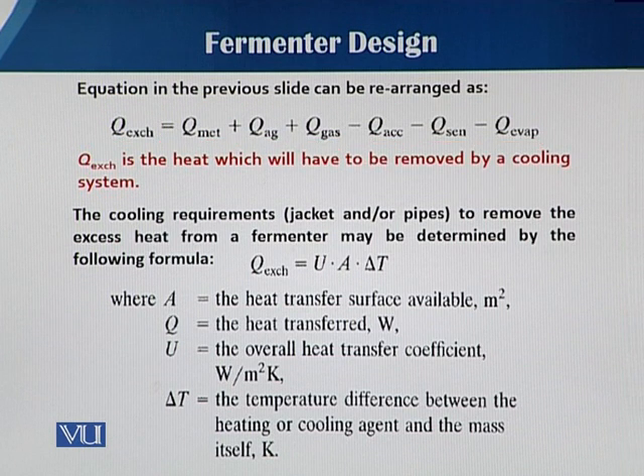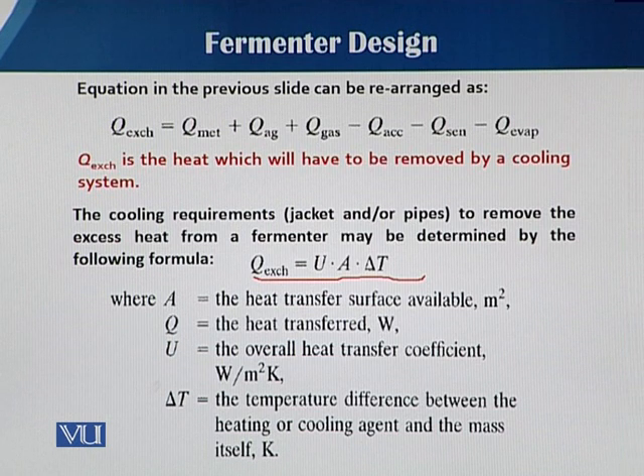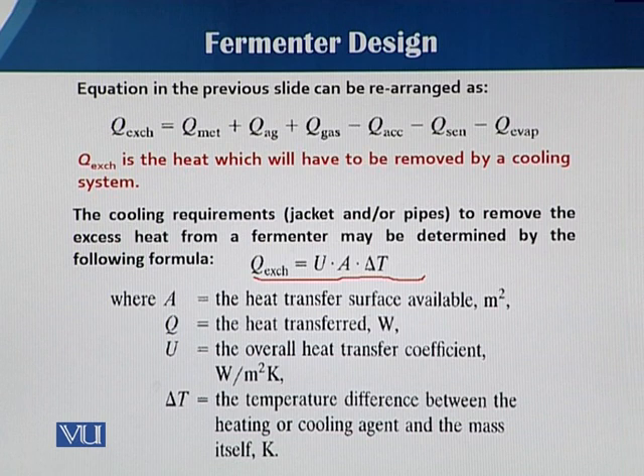When we know how much heat is required, we use the equation: Q_exchange = U · A · ΔT. Here A is the heat transfer surface area available — as already discussed, a jacket provides less surface area while cooling coils provide more. U is the overall heat transfer coefficient and ΔT is the temperature difference.